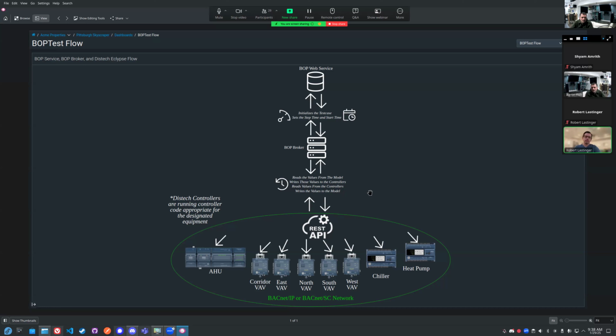Now, the user would set up what points they want to write to in the controllers, and there are JSON files that match the point in the BOPTest web service to the BACnet object or input you want to exchange with. That's all set up, and like I said, it's in the repo for the multi-zone office simple air. Let me bring that up.